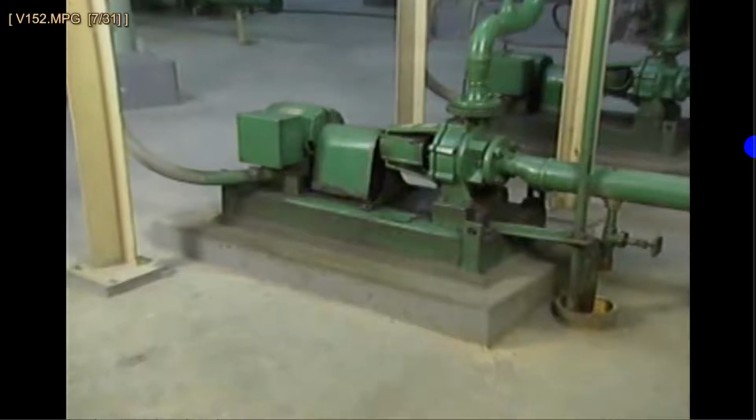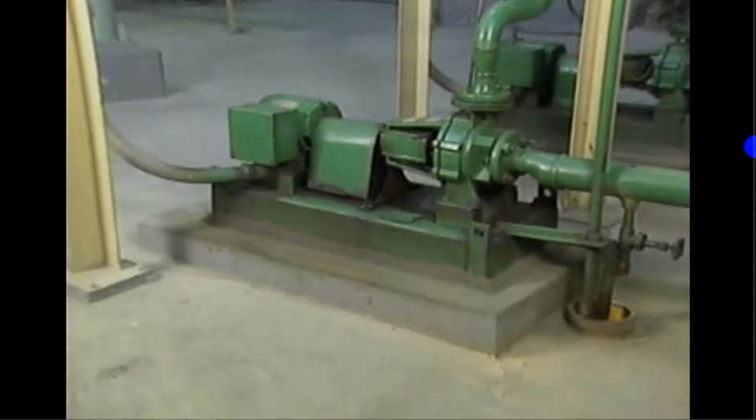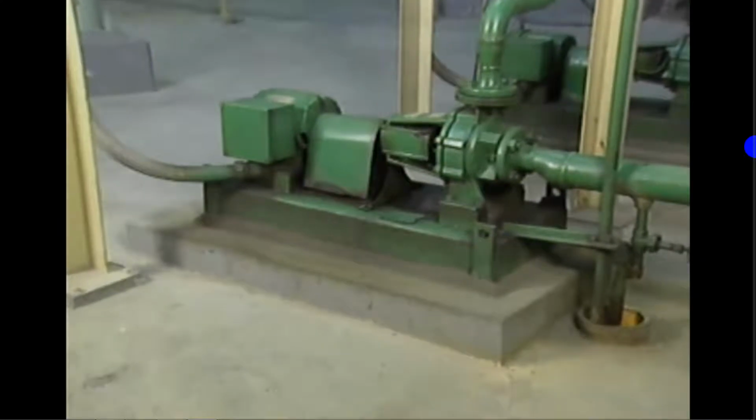A lot of factors can affect the alignment of the shafts between two pieces of rotating equipment. But not all of those factors involve the rotating equipment itself. For example, shaft alignment can be affected by the condition of the foundation or base plate that supports the stationary and movable components. Checks should be made on the equipment foundation before any alignment procedure begins.